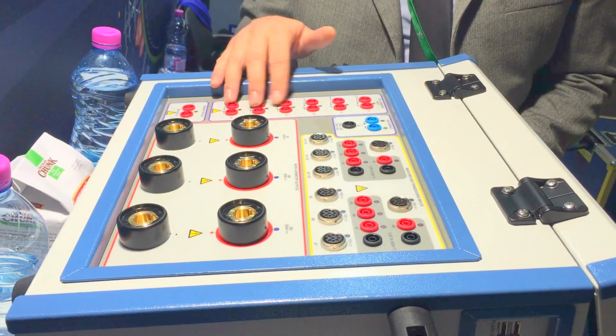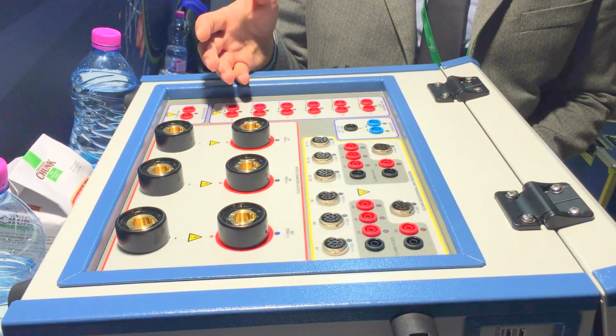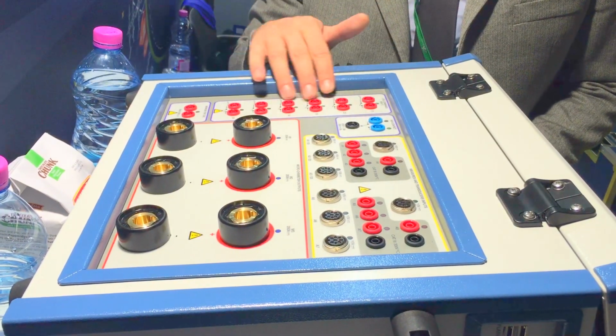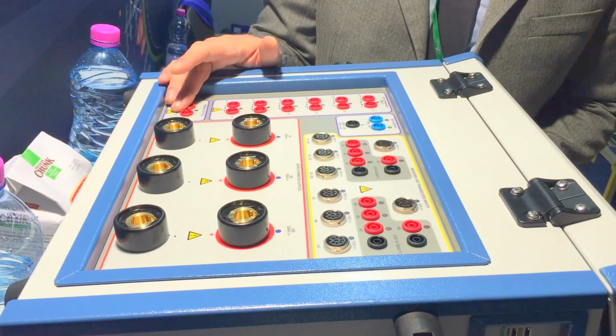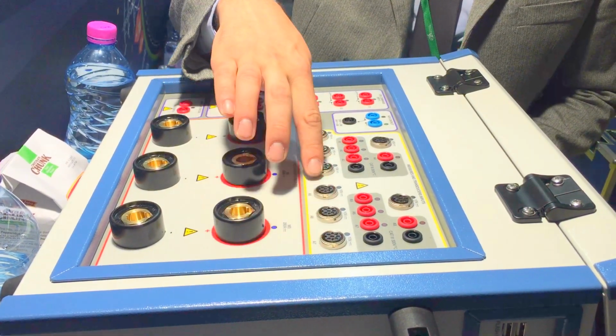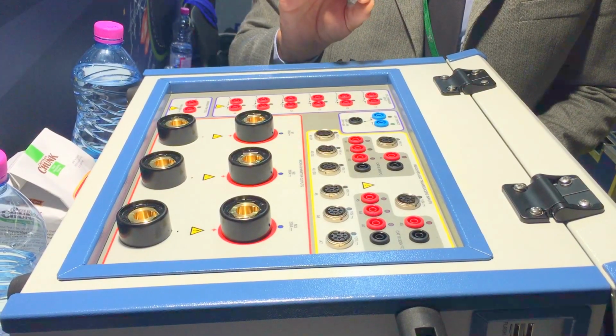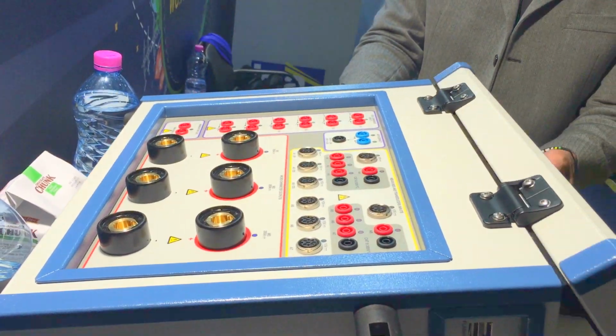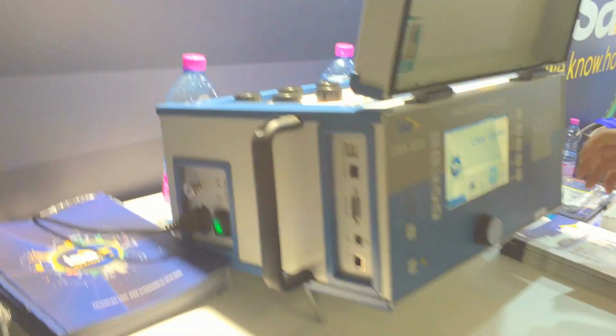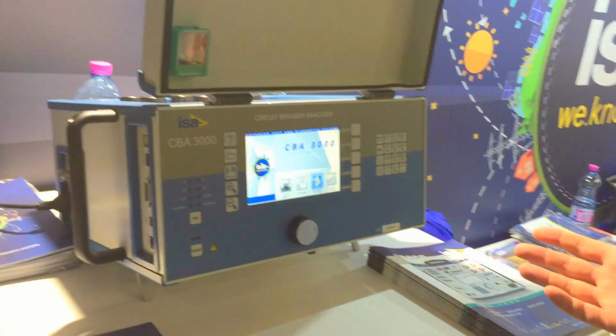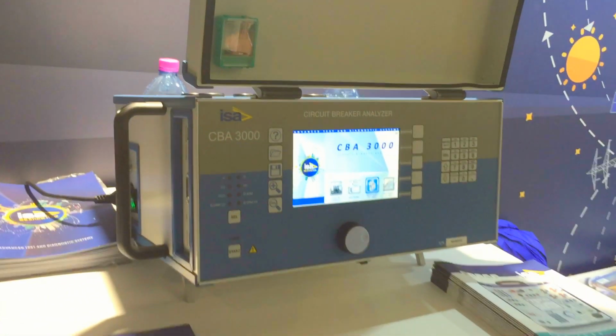The device can have up to 6 commands. Standard it would be either 2 or 4, but here you can have up to 6 commands, minimum trip coil, the ability to use travel transducers to check the movement, and also we can check now the screen. The screen allows us to do all the tests without using any software. Of course, if necessary, you can use the software.